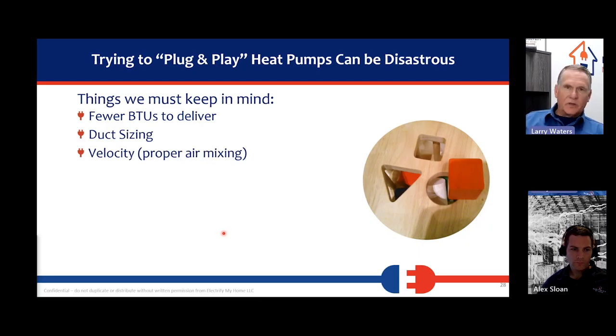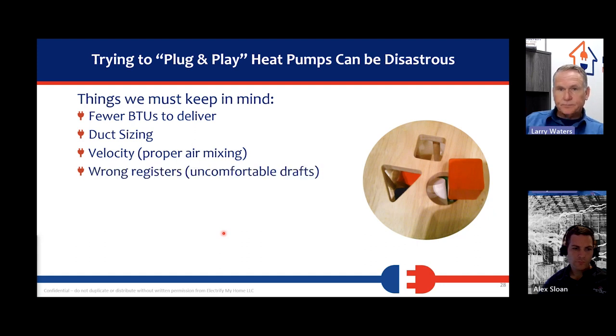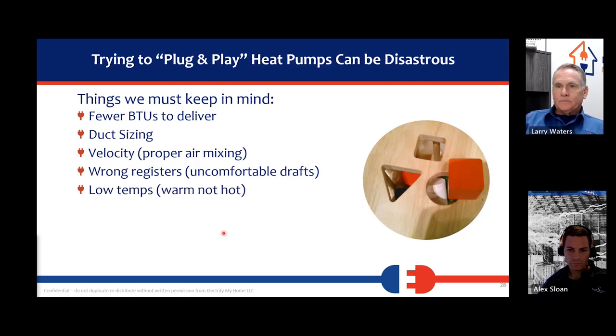We need to have proper velocity for air mixing, and we need to keep the air from blowing on the occupants. We need to change the registers in these houses, people. When you're installing a heat pump in a house, especially with ceiling registers, and you keep those three-way registers in there, when this heat pump is heating the house with air that's very close to the room temperature and very much cooler than your skin's temperature, it's going to feel like cold air blowing on people. We can't blow the air on people with heat pumps. Change the registers.